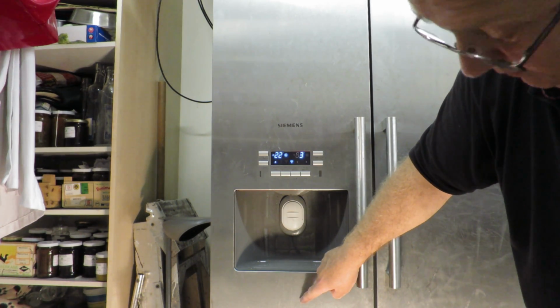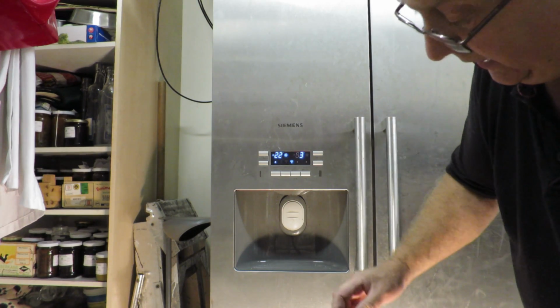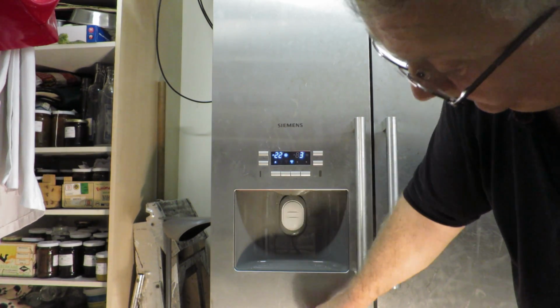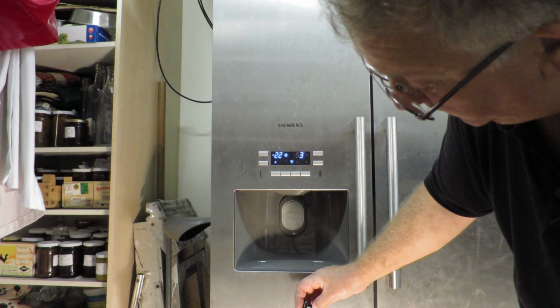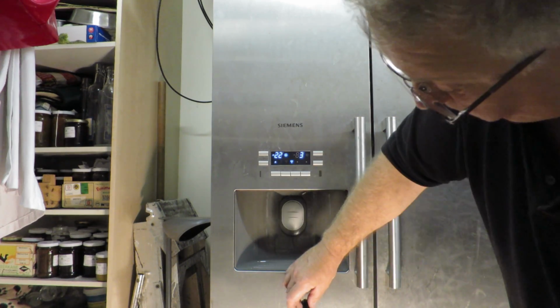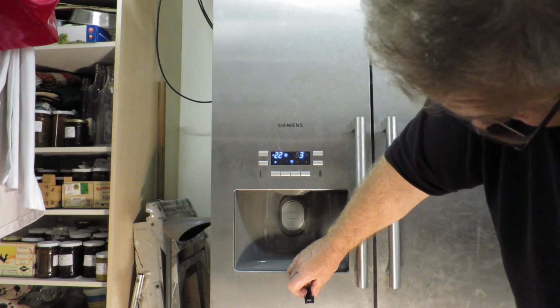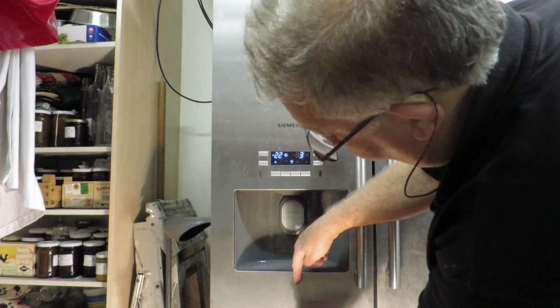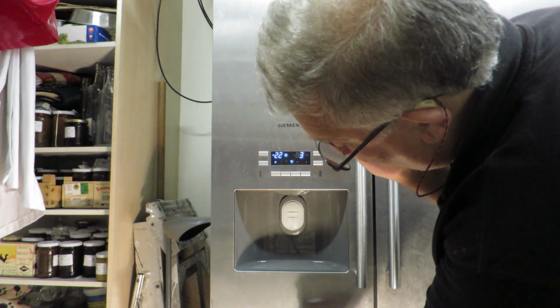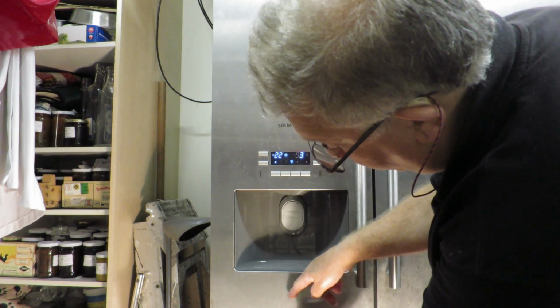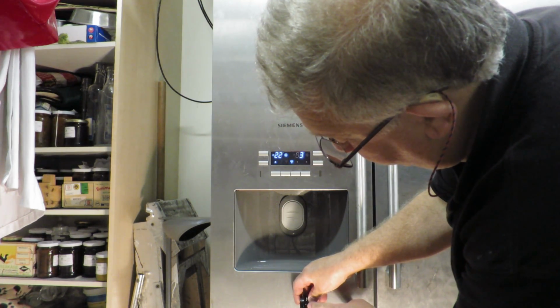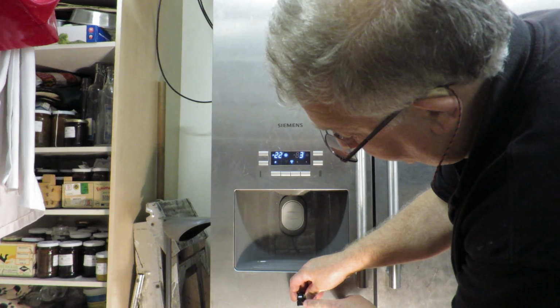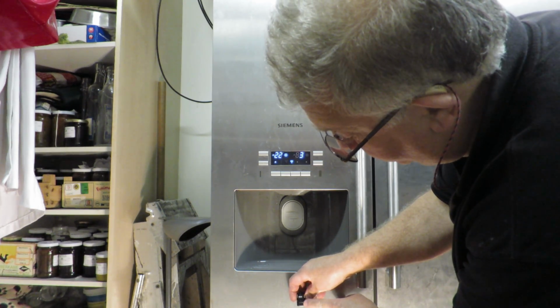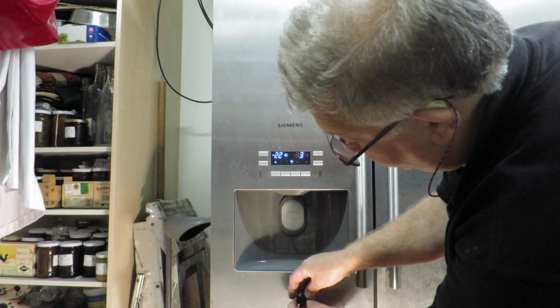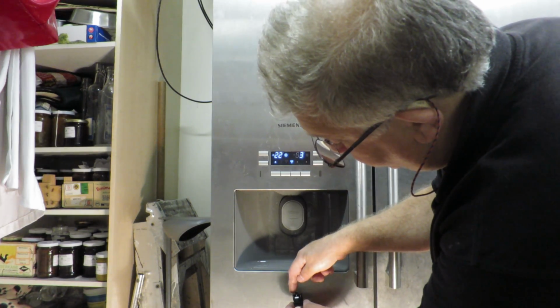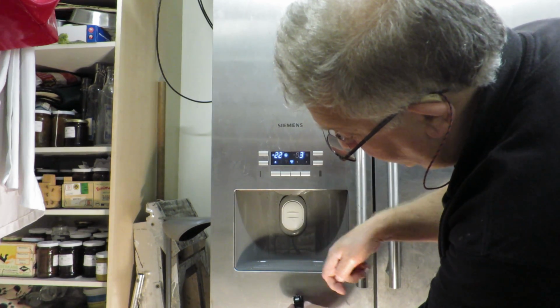Both coils fire up when it starts, and this unit, a PTC switch, goes across the bottom two pins, and essentially it allows the current from the top to go to the start coil for a time. I think this has a little heating coil and a temperature-sensitive resistance or relay, whatever - it's called a PTC. After it started, it will cut one side and just go to run.